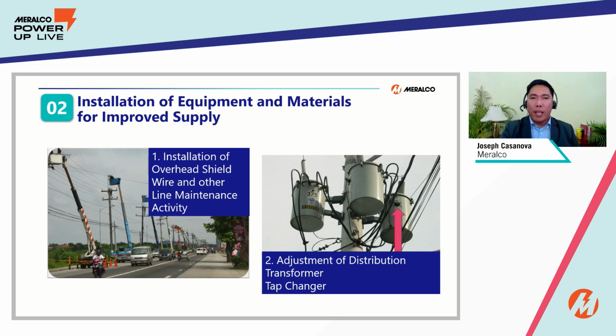Okay, so the next one is the adjustment of distribution transformer tap changer. So since the voltage of customers varies depending on the distance from the substation, our transformers are equipped with this tap changer to make sure that voltage serving our customer is well within the plus minus 10% na allowable voltage variation as discussed by Engineer Al a while ago.